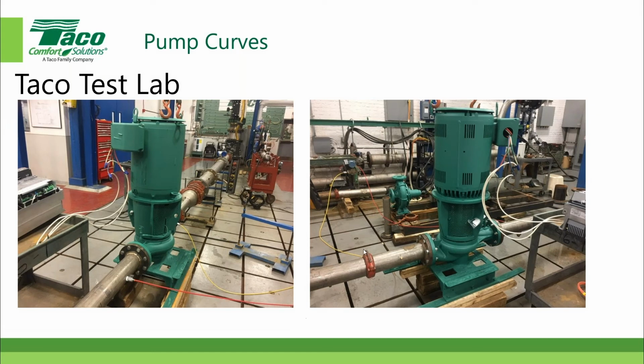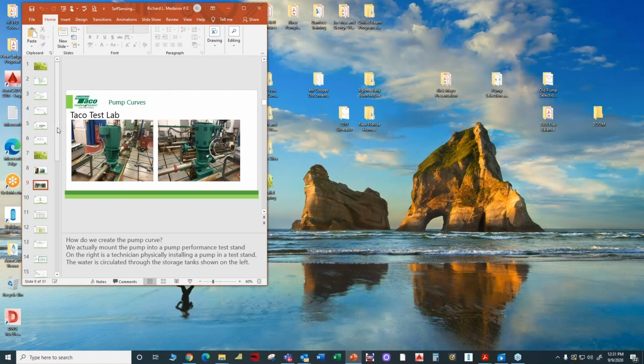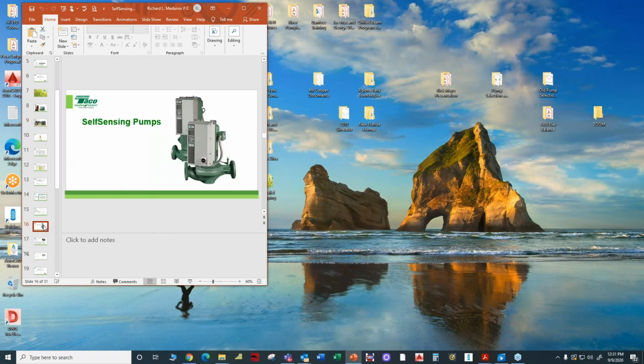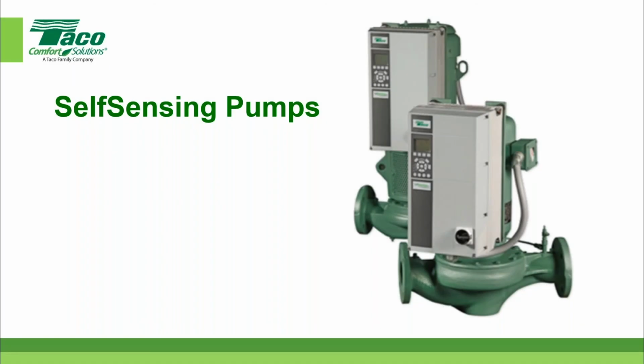All right, so let's continue on here. Let me just go down to where we get into the self-sensing pump. When we talk about a self-sensing pump, in a moment I'm going to talk about collecting the data in the laboratory, but I want to point out that the self-sensing pump includes multiple components here. A self-sensing pump includes the electric motor, that's the guy in the background here. It includes the variable frequency drive, that's the gray guy in the front, and it includes the pump, that's this guy right here. The one in the foreground is a KV, which stands for close coupled. The one in the background has the same thing: the electric motor, the smart drive, and the pump.